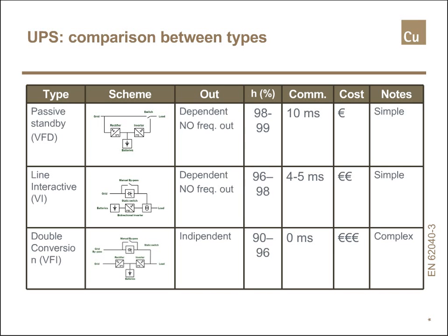The first type is the simplest and therefore also the cheapest. But as usual, when cost and sophistication are limited, we have some limitations. For example, we can expect a dip in the supply when moving from grid to battery operation, and in any case the output is dependent on the input, as described in the name. The second class is something in between.